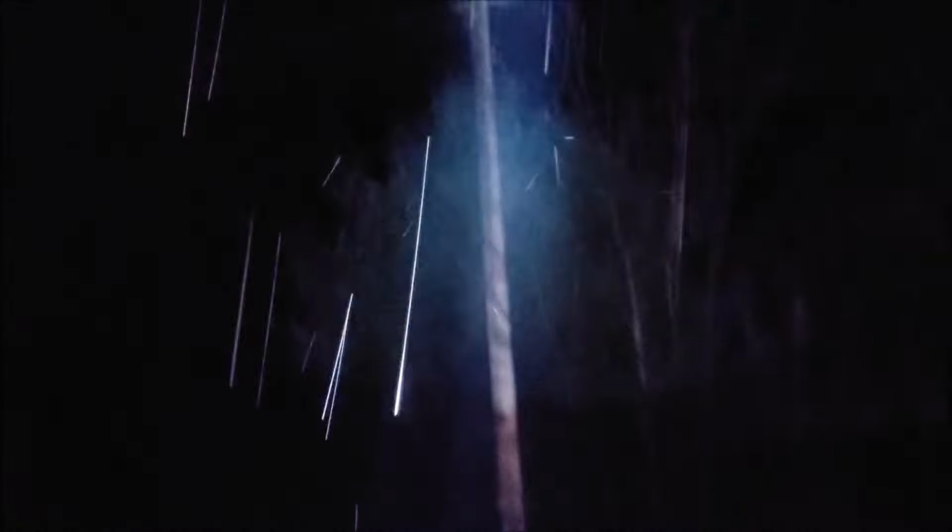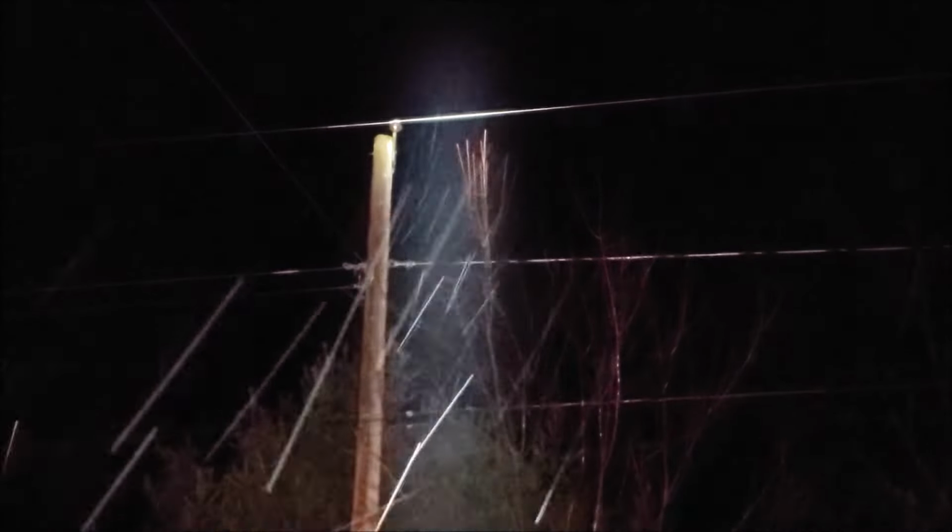All right, so take a look at this here. Let's see, there's a little white spot in the center of that insulator there. It could be nothing, but I'm wondering if it isn't cracked and maybe that white spot's the top of the pin showing through the insulator. If it is, that's a pretty good find. There's about 300 poles in this line.